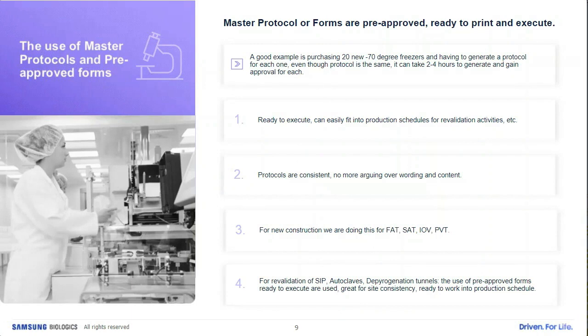That gives you the idea of what master protocols are. It's just pre-approved protocols ready to execute. It cuts out that pre-approval step. For revalidation, some of the things we've done previously is you could do master protocols for that. So if I'm doing an autoclave on a yearly basis, we can generate a master protocol that says, okay, these are the steps I'm going to perform every year for my autoclave validation, where I'm doing the Bowie-Dick test, the leak test, an empty chamber, a minimum load, and maximum loads. They're already defined in that protocol, and I print that protocol out and go execute.